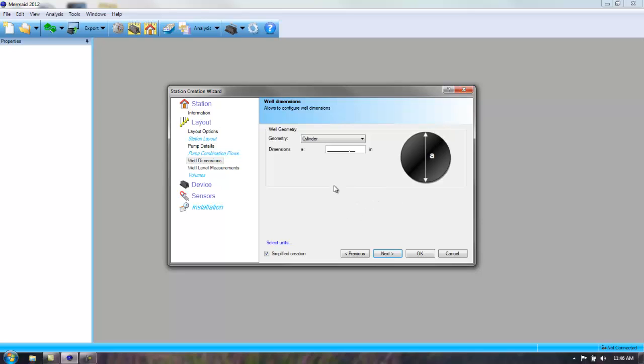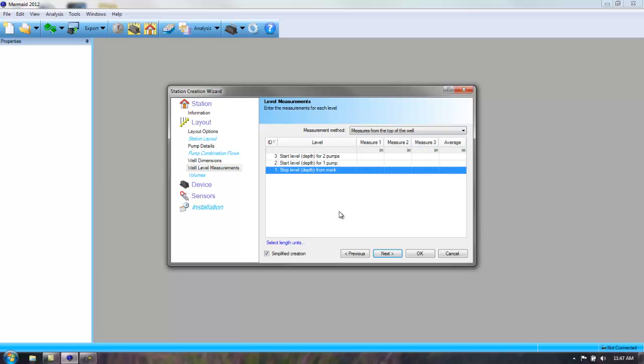I'm going to use the most popular one that I've run across, which is 8 foot. Now my options, I have it set up in inches, so that would be 96 inches. The level measurement, we measure from the top of the well or the bottom of the well. Typically I monitor from the top of the well using a level device or a tape measure type of device. If you're measuring from the bottom of the well, that will most likely be a pressure transmitter or transducer that is in the well measuring the level above it. For this case, we're going to measure from the top of the well, but there's other selections, as I said.